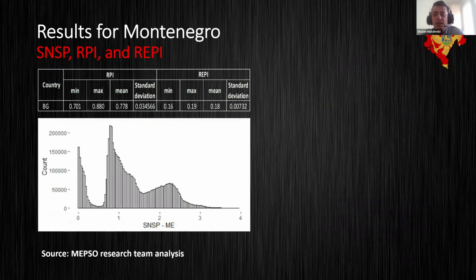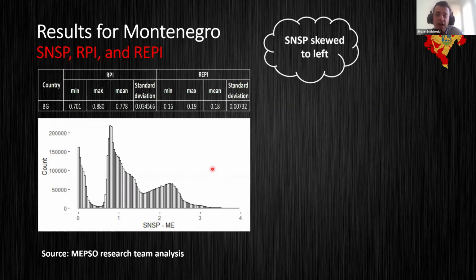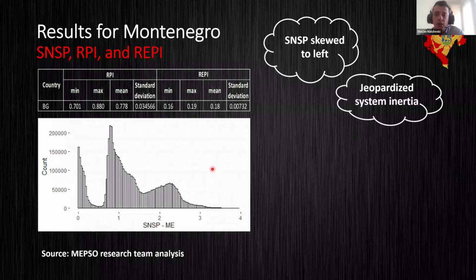On the other hand, we have the results for Montenegro. Here, in the table, we have the data for the renewable penetration index and renewable energy penetration index, and below we have the histogram for the non-synchronous penetration ratio. From the histogram, we can conclude that the data is skewed to the left, or centered. But what's important is that most of the values are between 1 and 3, which proves that their system inertia might be jeopardized in the future, or that they'll have to rely on the neighboring power system to keep their frequency in check.